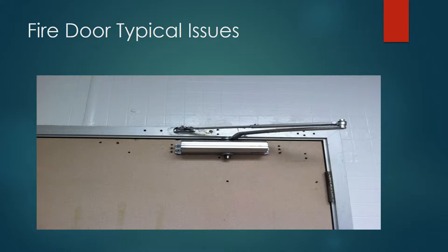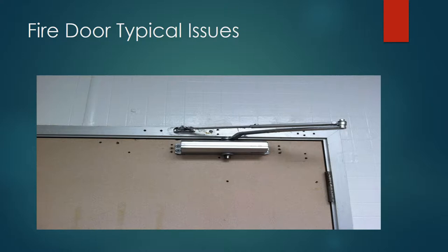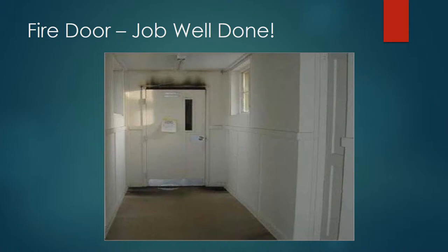How about this one? Let's count the holes — there are approximately 24 holes in this door. You have to wonder why, and obviously the first question is whether they've put in different closers. This is probably a very heavily used door that's been damaged and worn out, and they've kept trying different closers to satisfy issues and keep the door working. This is an obvious violation.